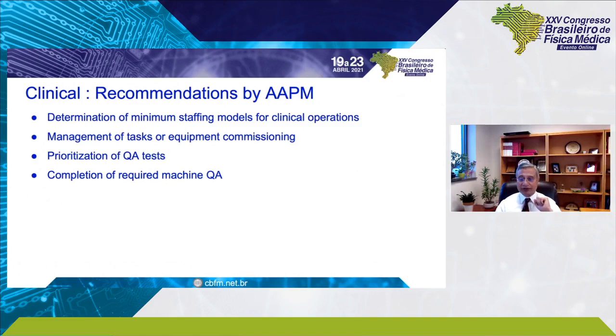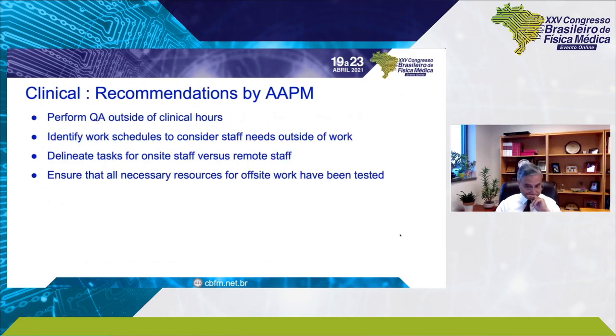Prioritize your QA tests by considering the impact on patient care and resource availability. Complete the required machine QA as quickly as possible in case the staff availability is reduced later on. Perform QA outside of clinical hours to minimize the impact on clinical schedules.